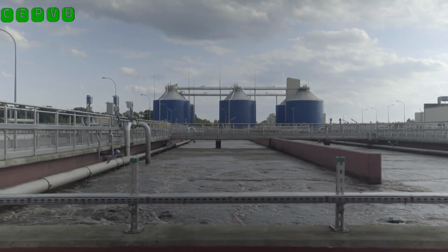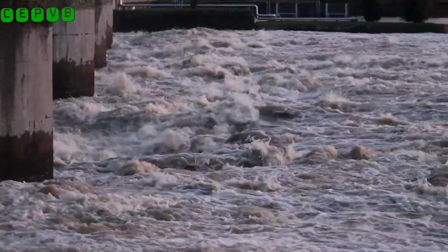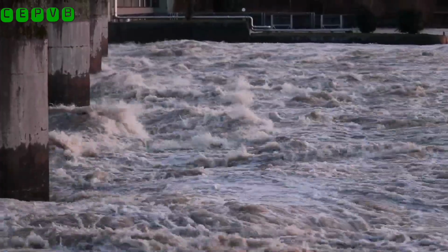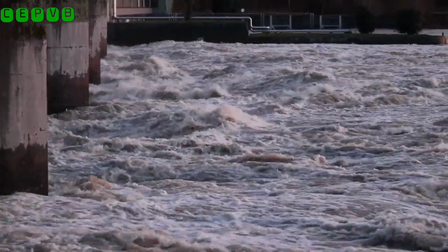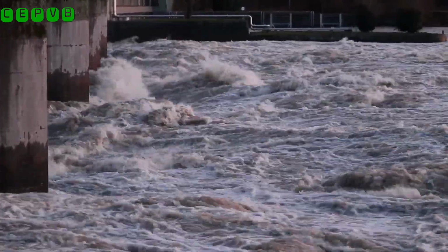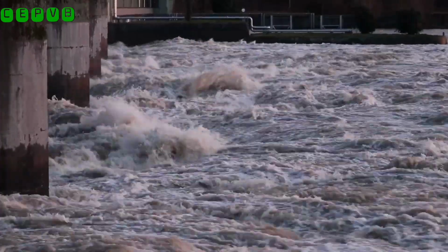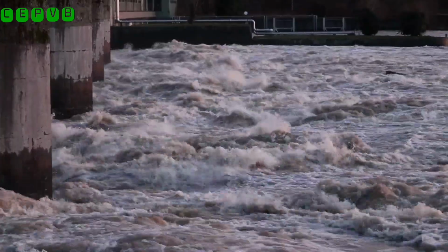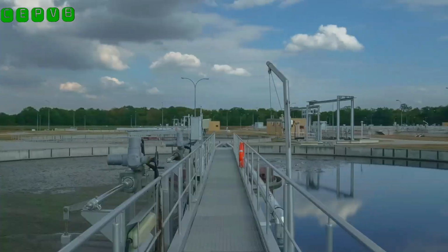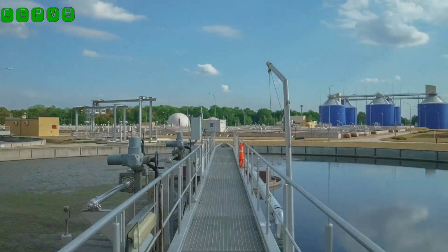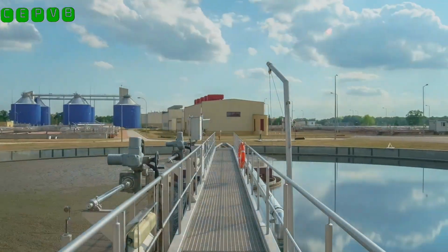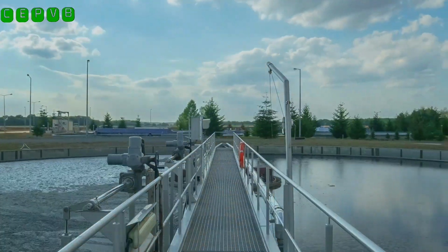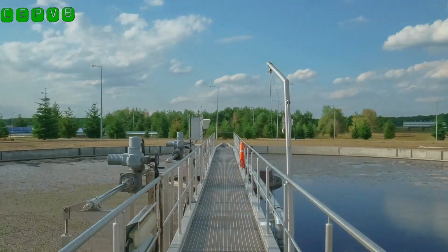Filtration. The following step is generally running the water overflow into gravity sand filter basins. These basins are big areas where they put 2 to 4 feet of sand, which is a finely crushed silica sand with jagged edges. The sand is normally installed in the basin at a depth of 2 to 4 feet, where it packs tightly. The feed water is passed through it. On smaller systems, you might go with a packed bed pressure multimedia filter versus gravity sand filtration.